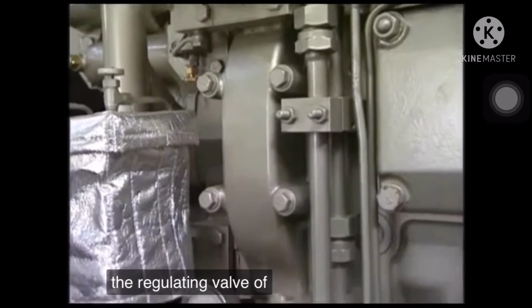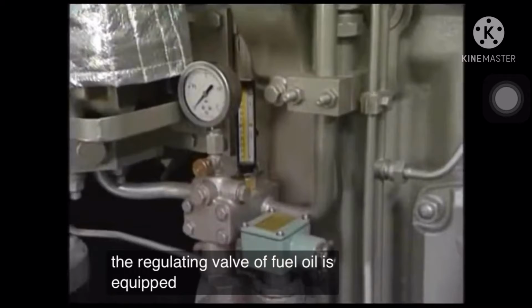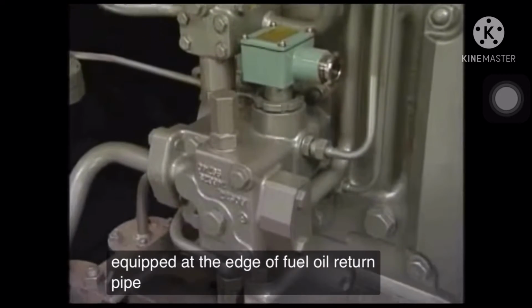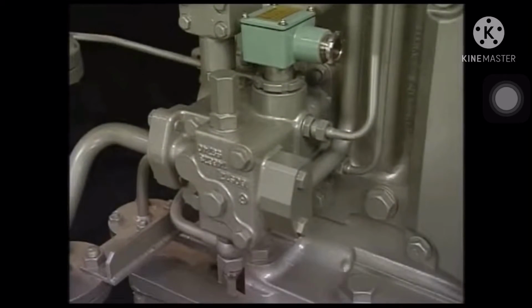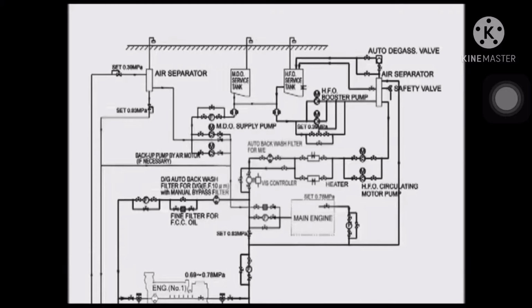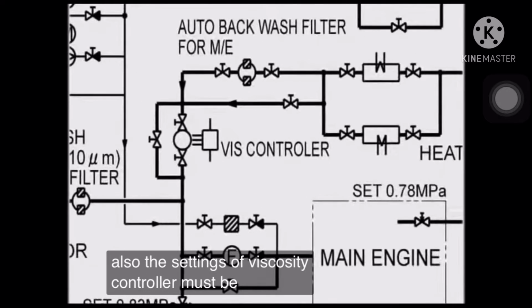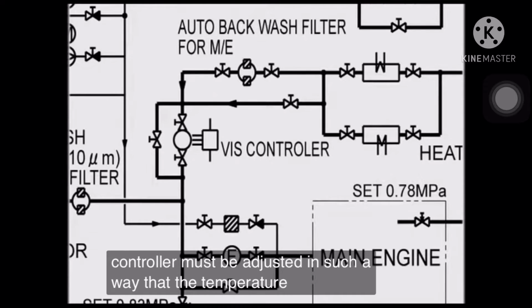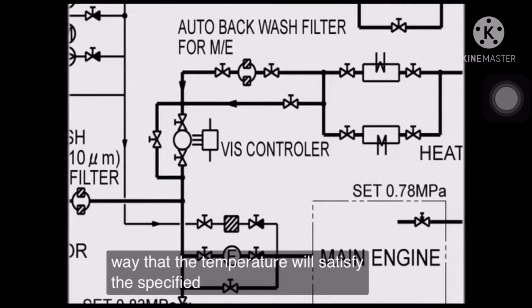The regulating valve of fuel oil is equipped at the edge of fuel oil return pipe. Also, the settings of the viscosity controller must be adjusted in such a way that the temperature will satisfy the specified value at the engine inlet.